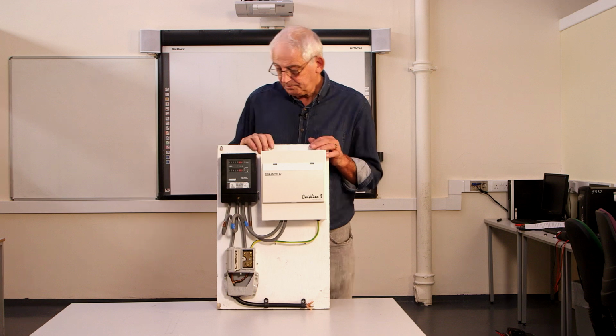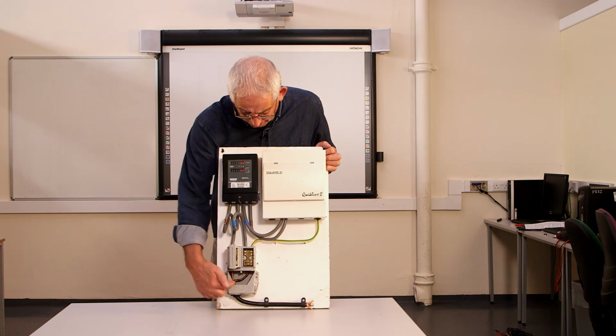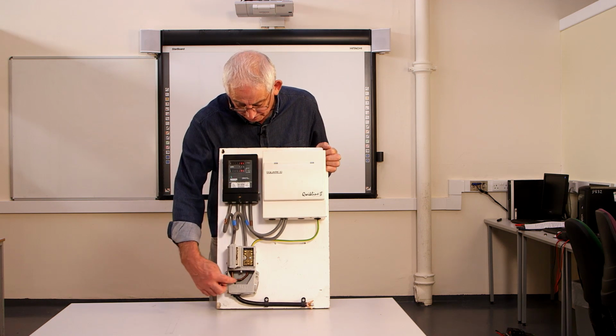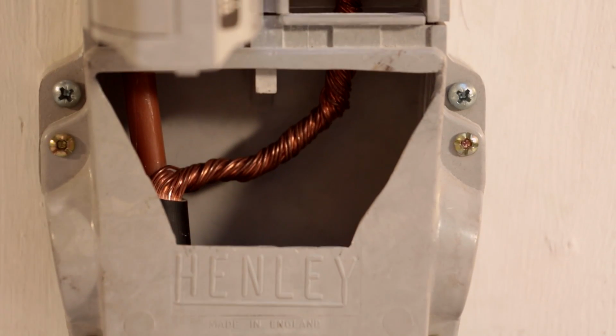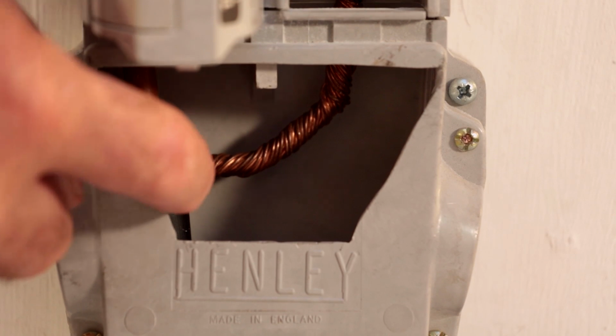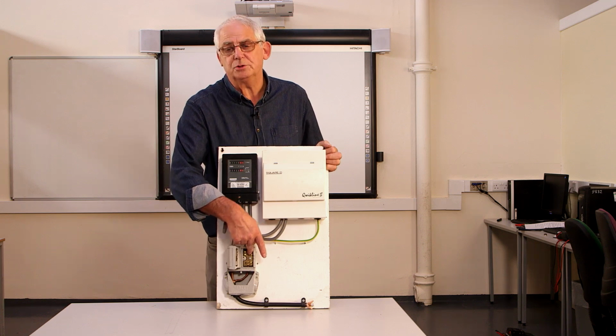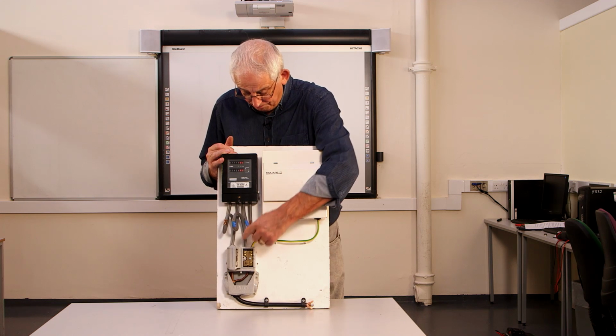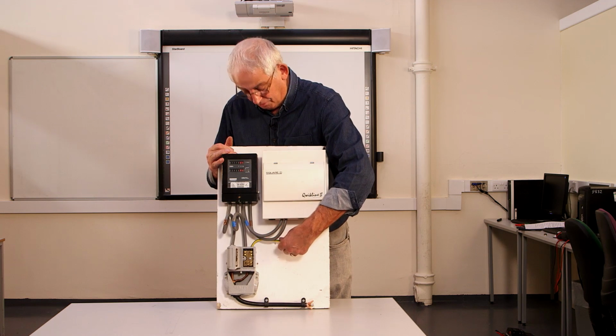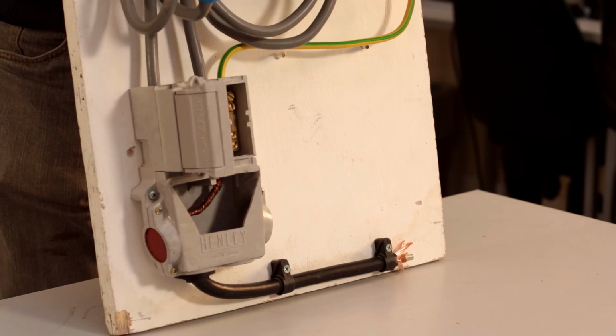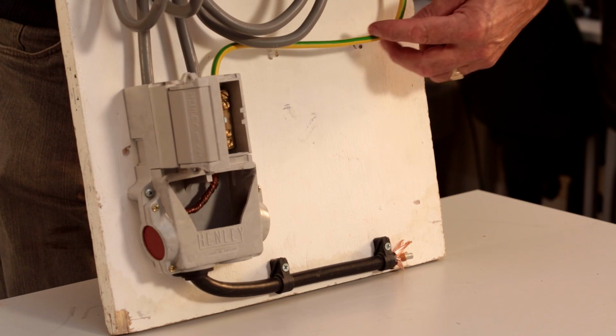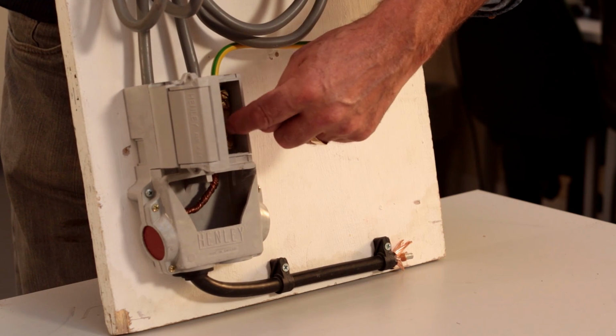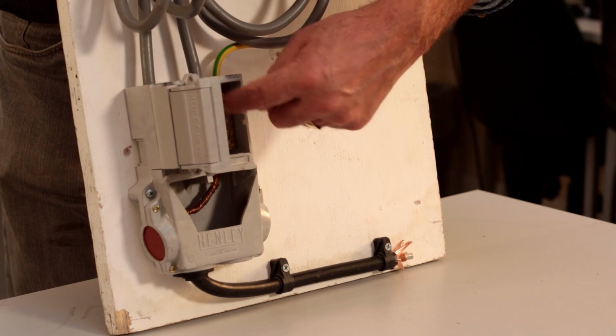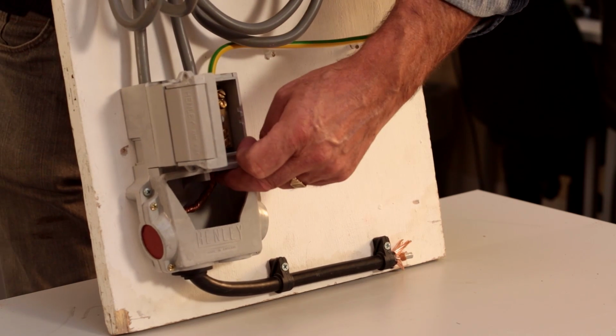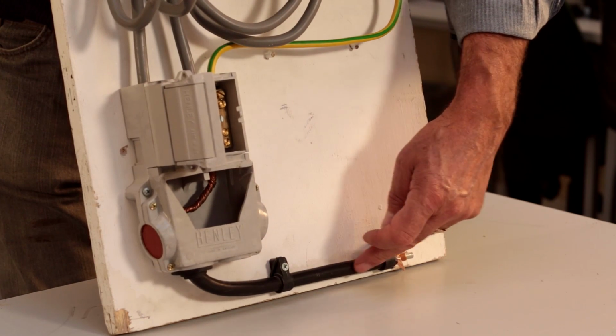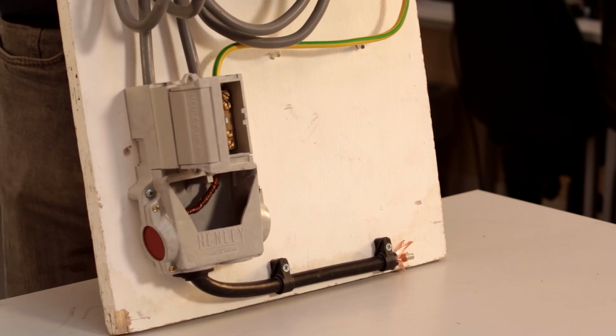When we get to the service head, this has been cut away a little bit, and you can see inside that actually the neutral conductor, or the PEN conductor, is split away from the line conductor, connects into the neutral bar here, and then from the neutral bar to our main earthing terminal, we would have an earthing conductor. If there's a fault, the fault current will flow down the earthing conductor into the neutral terminal, which is an earth and neutral terminal, through the PEN conductor, through the outside sheath of this cable, into the star point of the transformer.